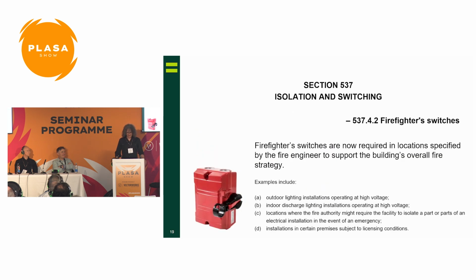What have we got next? Firefighter switching and isolation switching, chapter 53, section 537. This is where, conventionally, you've seen these things in buildings where you've got, could be a shop, for example, could be a burger or kebab shop, that kind of thing, where you've got neon signage on the outside. And there's been a requirement that you have a firefighter switch on the outside. What's gone on here is that where you've got neon signs, for example, operating above 1,000 volts, you need that switch. What's been added in C and D here is that the person from the fire brigade, from the fire authority, might say that because you've got battery storage within the building, for example, that's another risk. Therefore, we want you to have a firefighter switch for that building.